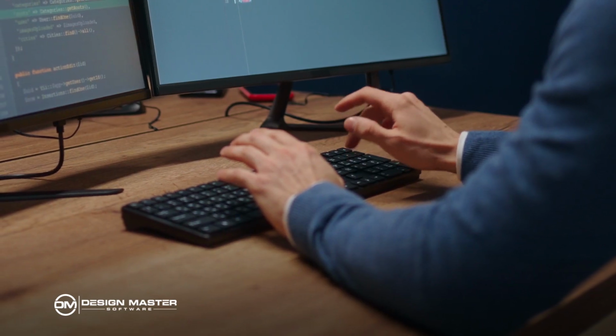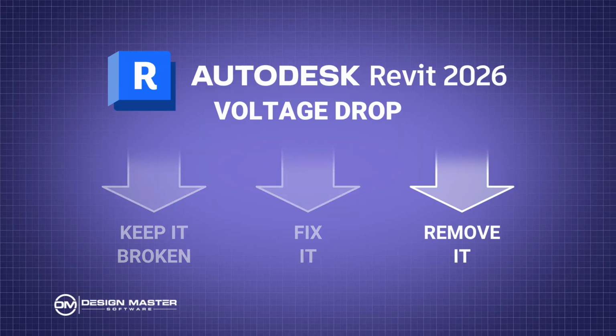They could have fixed it, and in fact with Revit 2026 they took the first steps toward doing that. They took their wire sizes, they made it so that the engineers could actually set the wire sizes, they expanded that whole feature, but they didn't take the final step necessary for voltage drop to add actual impedances to those wires and then use them to calculate the voltage drop. They're very, very close, but for whatever reason, they did not choose to make that next final step to get a correct voltage drop. Instead, they went with the third option, which is to remove voltage drop entirely from the program.